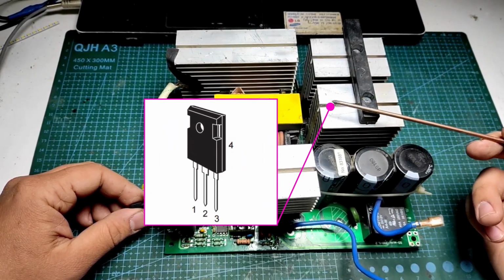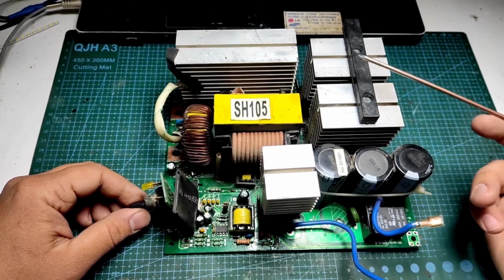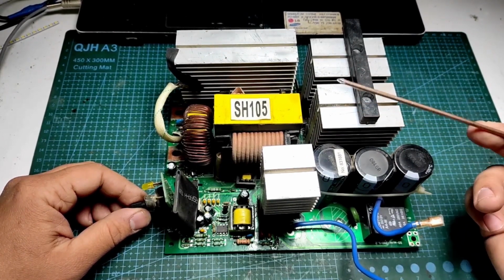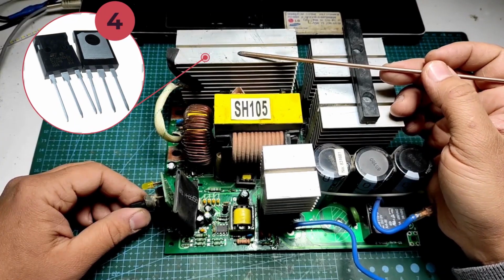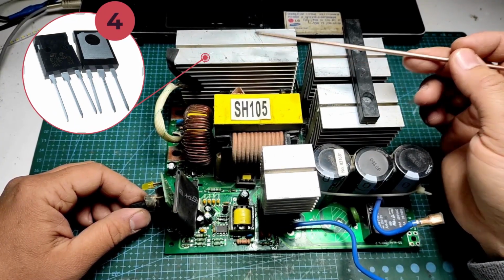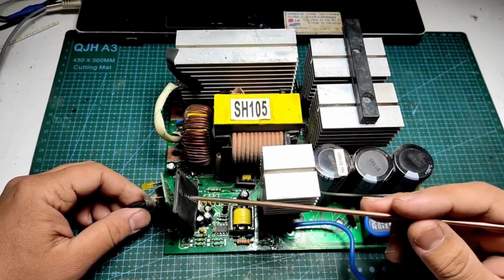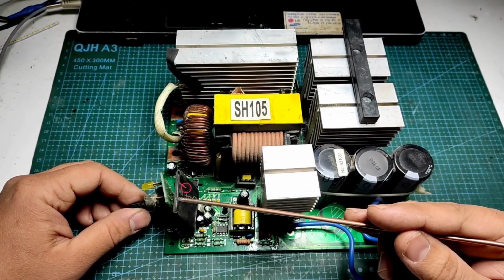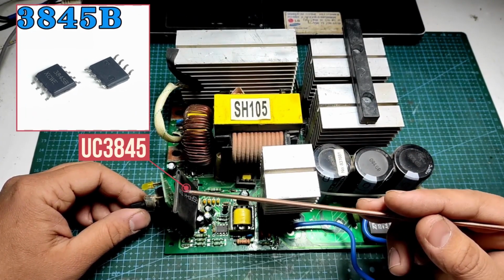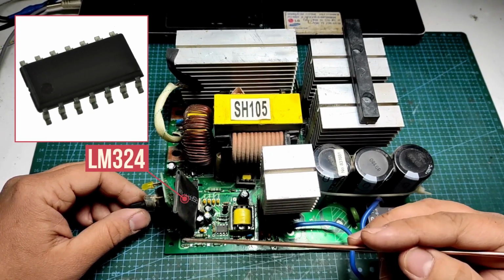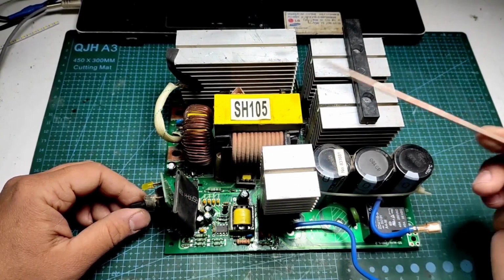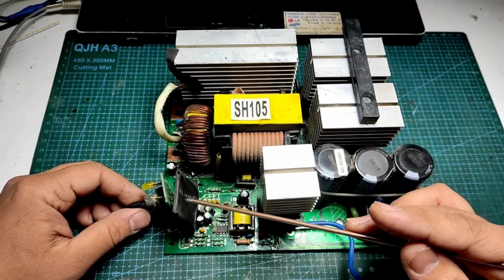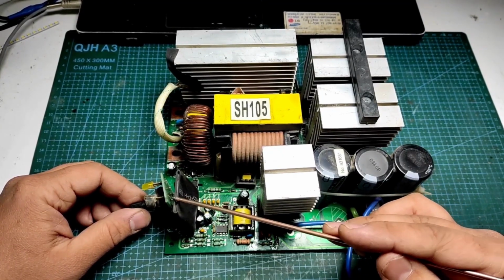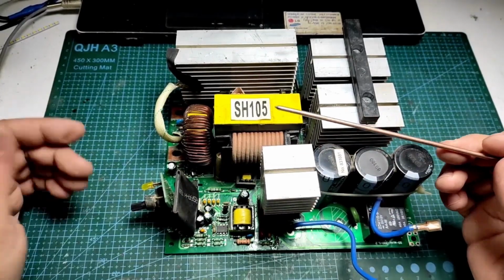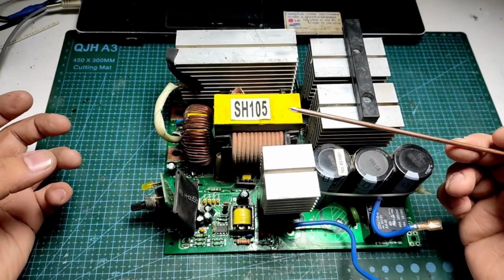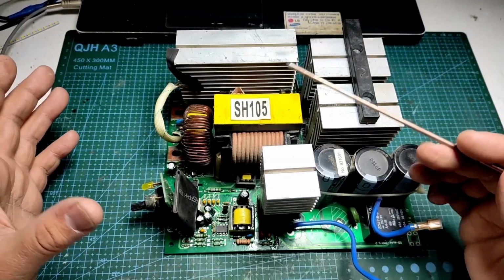If we look at the current configuration, the power transistors are rated at 38 amps and 600 volts, with 4 units installed. On the output side, there are 4 power diodes. As for the control circuitry, the control unit is built using the UC3845 and LM324 integrated circuits. This control section is used to drive the transistors and to monitor and manage the protection functions to protect the main output against short circuits, including anti-latching, anti-stick protection, and other types of short circuit conditions.